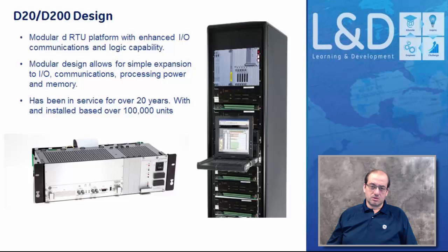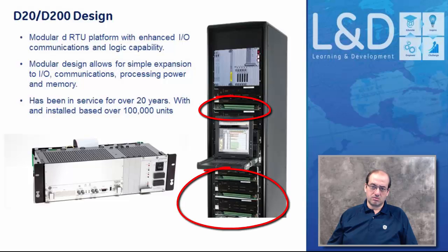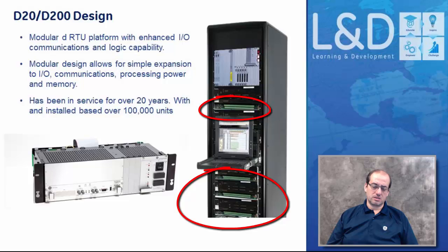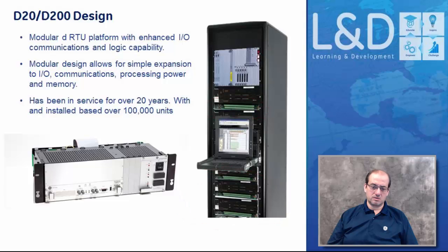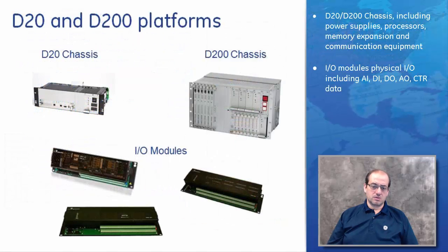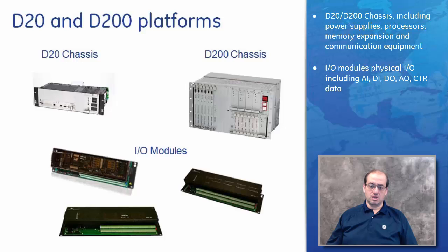The D20 is a modular design that allows for simple expansion of I/O cards. You can have as many I/O cards as required to collect data from the substation. These I/O cards are wired directly to a marshaling cabinet or directly to a transducer or sensor in close proximity. The main components are the D20 chassis — horizontal or vertical — and I/O cards, which can be digital I/O, analog I/O, digital output, or combination cards with digital input, digital output, and analog inputs.